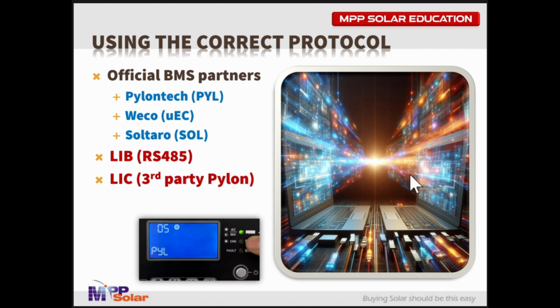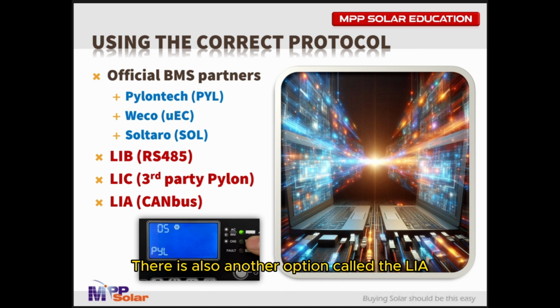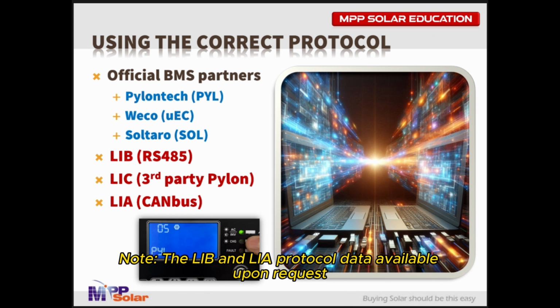Next, LIC is basically the same as Pylontech, and this setting is reserved for any third-party battery manufacturers that are following the Pylontech protocol. So you may use LIC or PYL, they are essentially the same. There is also another option called LIA, which is the CAN bus equivalent of LIB but for a different interface. It's important to know not all of these profiles may exist on all MPP Solar inverters, so be sure to check the user manual or LCD display directly to see what options are available to you. Note, the LIB and the LIA protocol data are available upon request.